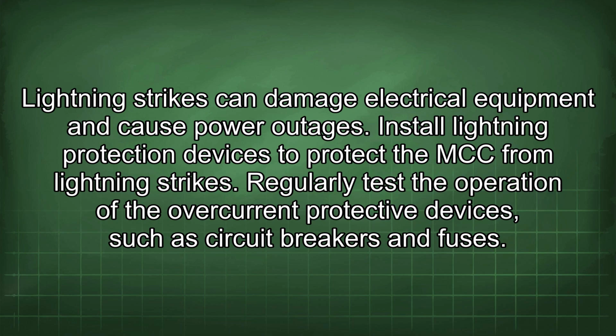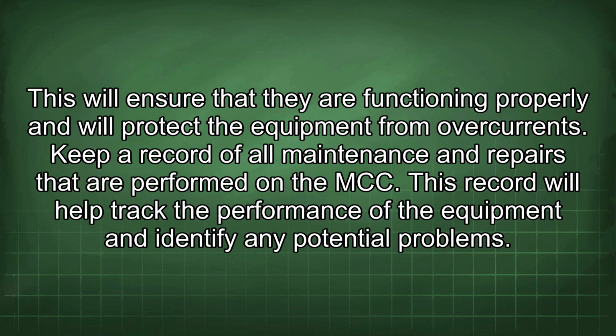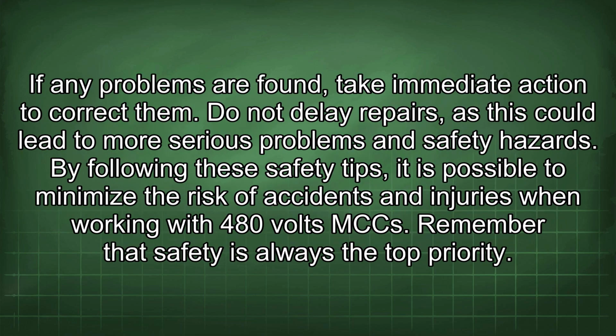Regularly test the operation of the overcurrent protective devices, such as circuit breakers and fuses. This will ensure that they are functioning properly and will protect the equipment from overcurrents. Keep a record of all maintenance and repairs that are performed on the MCC. This record will help track the performance of the equipment and identify any potential problems. If any problems are found, take immediate action to correct them. Do not delay repairs, as this could lead to more serious problems and safety hazards.